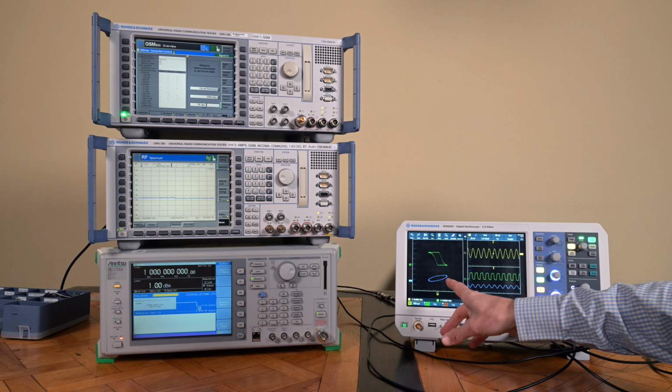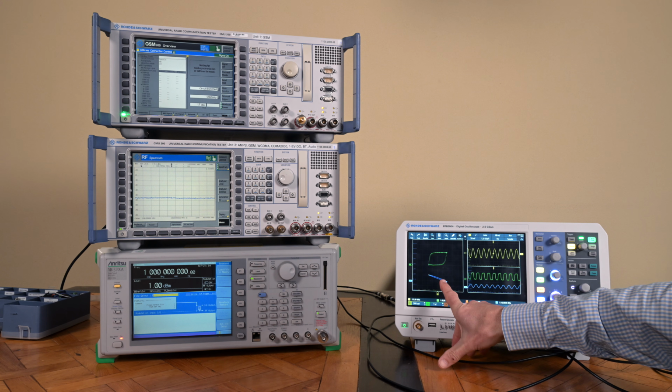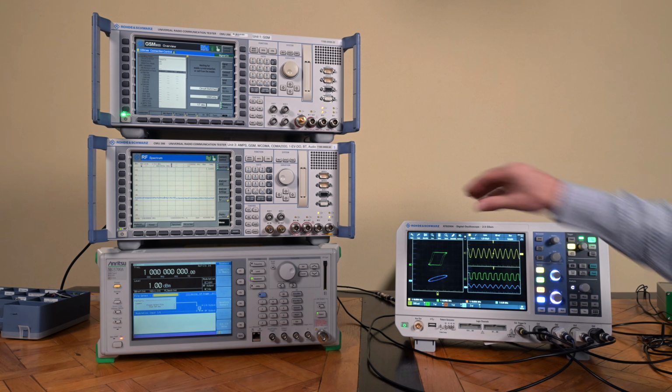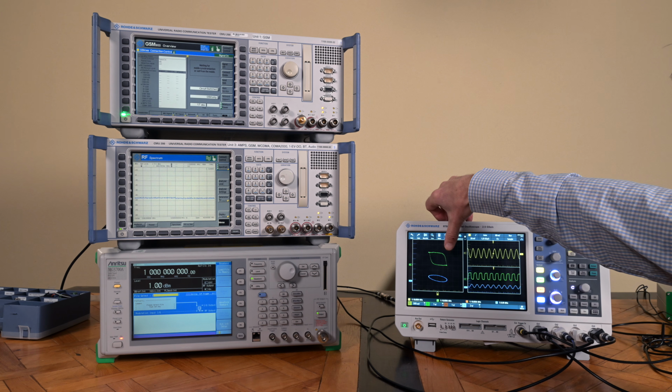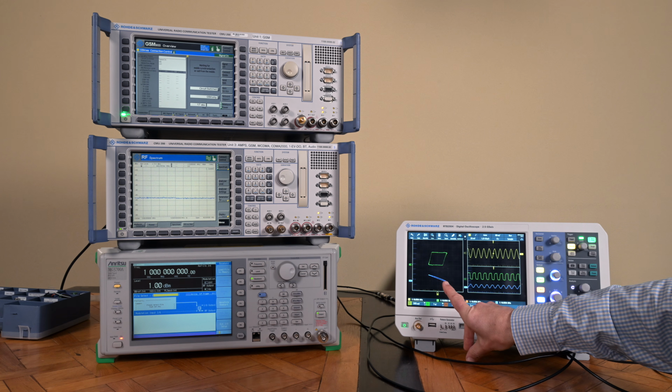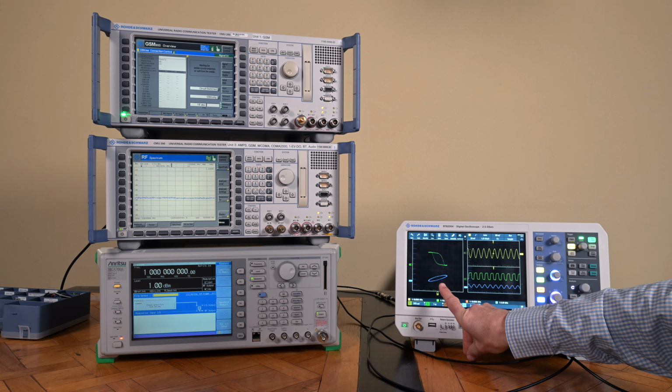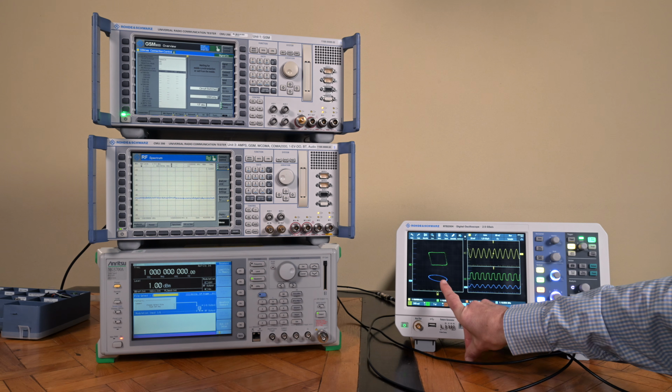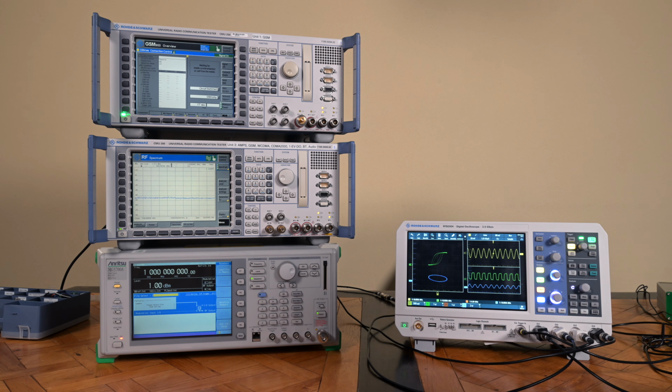And we can observe here how many seconds it takes. So this one is basically opening and closing fully every second or so. So it's 0.1 ppm off. This one is a little bit slower, or a little bit more accurate, because it takes 2 or 3 seconds to go through the whole cycle here.